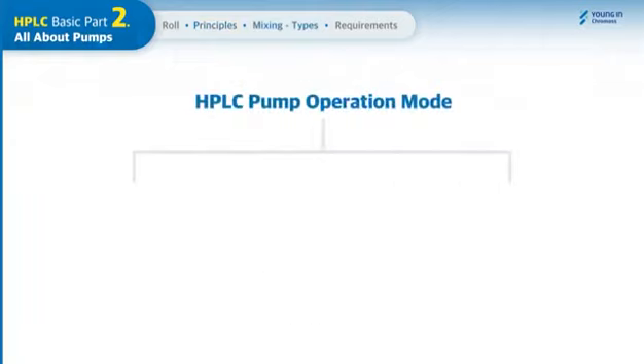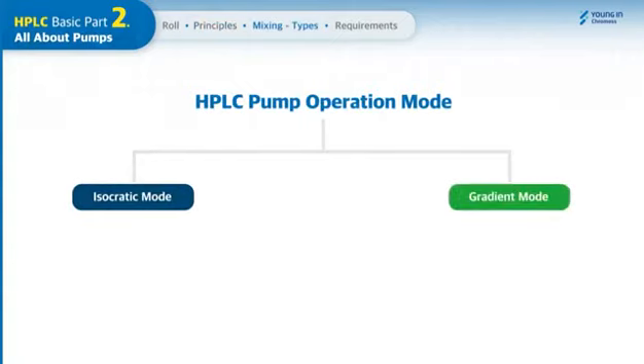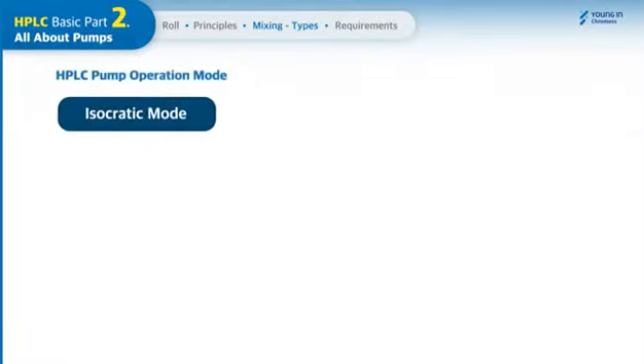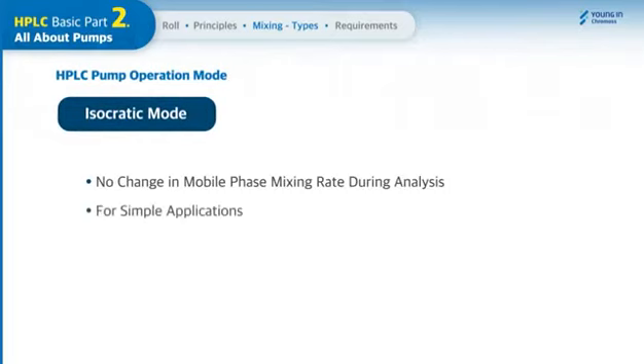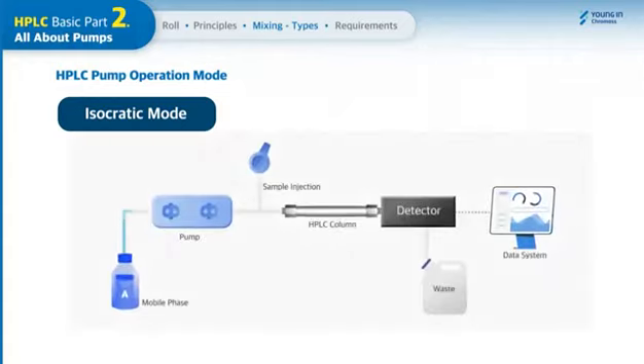The pump operation mode can be categorized into isocratic mode and gradient mode, depending on mobile phase mixing. In isocratic mode, there is no change in mobile phase mixing rate during the analysis, and it's recommended for the simple application that needs to analyze one or two analytes. Due to the constant composition rate of mobile phases, it provides superior results in repeatability. Mostly, one mobile phase eluting line is used from the pre-mixed solvent in one bottle. This pump is called an isocratic pump that has one pair of pump heads with a single solvent line.